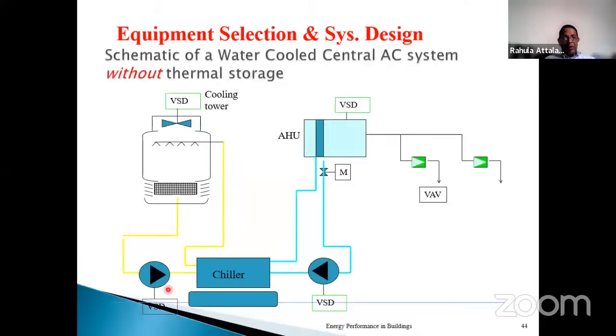Same thing, this is incorporating the entire system with VSDs. So you can have a VSD in your air handling unit. You can have a VSD in your chill water pump system, the water that goes to the chiller. And you can also have a VSD in the cooling tower and the condenser water system. Of course, the most important would be the first two, and the last would be the condenser. It's quite rarely used there. Of course, if it is, the decision will come from economic reasons.